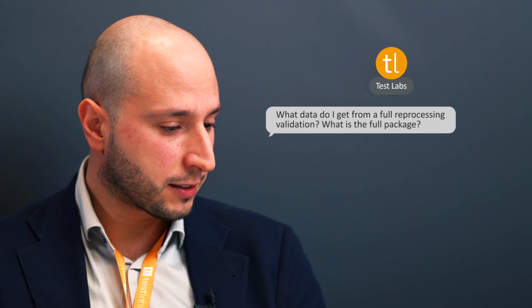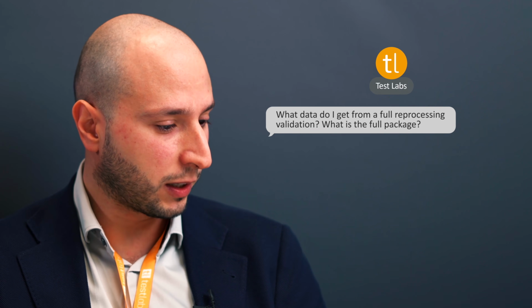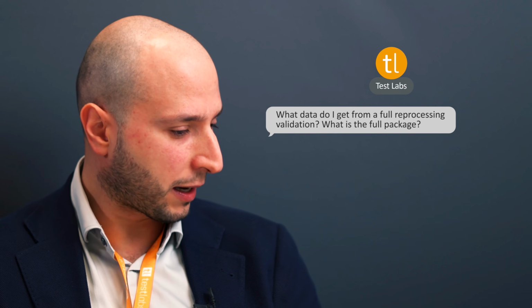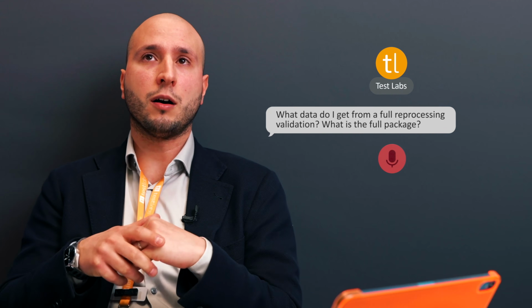Right, on to the next question, which is what data do I get from a full reprocessing validation? What is the full package, basically? Right, so ideally reprocessing validation covers a few areas, so many aspects, which is cleaning validation, disinfecting validation, sterilization, should you need it. Not all devices need sterilization. And ultimately is service life. So how long can my device be reprocessed, or how many times can it be reprocessed safely?